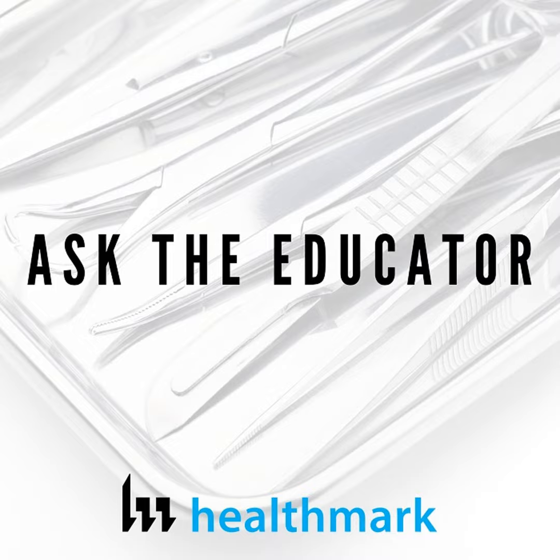A lot of times when I saw dirty instruments as an OR nurse, it was when we pushed something through a cannula or a lumen and then debris came out the end. And by then it's too late. You're already there taking care of the patient. So understand that equipment will help you produce a higher quality, safer surgical tray of instruments, but if you're not testing it, you don't know. And you could be possibly preventing all of that if you just run a simple test every day that you use this equipment. So I hope that I convinced you, because it is something I believe in, because I've actually seen positive results from this where we were able to make decisions and make things work properly right there in real time. And it's a powerful thing to be able to do.